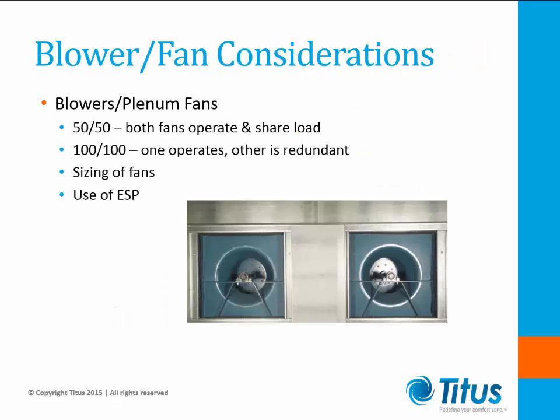It is important to properly select centrifugal fans to balance performance and cost. Larger fans are typically more efficient than smaller fans. It is also important to use external static pressure as your driving factor when selecting fans in AHUs. Don't match a competitor's total overall static pressure. Competitors' units have different internal static pressure drop with their components, yielding a different total static pressure on the unit.